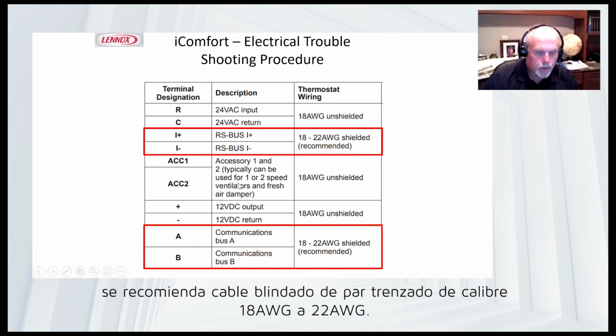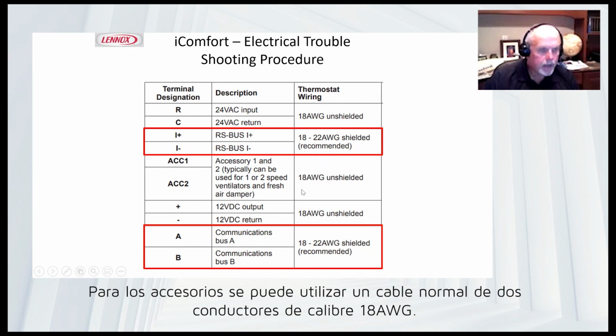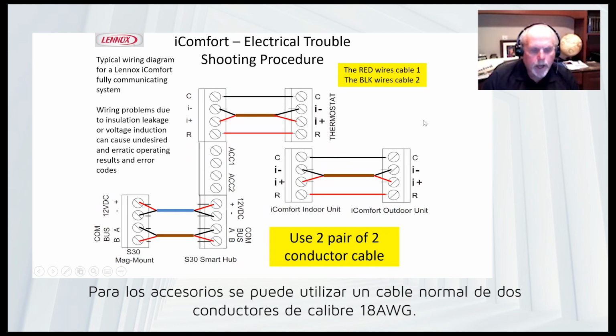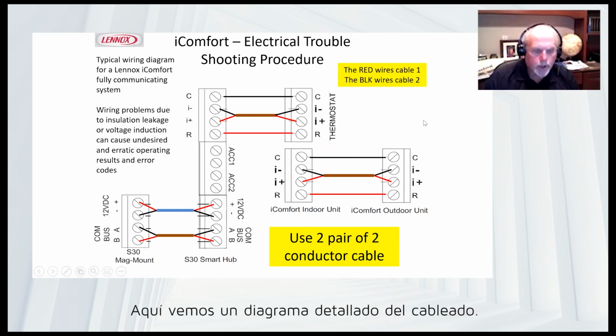Okay. For the accessories, you can use regular 18 gauge two conductor wire. And for the communication bus up to the display subbase, also shielded twisted pair. Okay, so all the way through on the communication bus, shielded twisted pair wire. That is what's recommended. Okay, here, just showing you a visual here of the wiring.